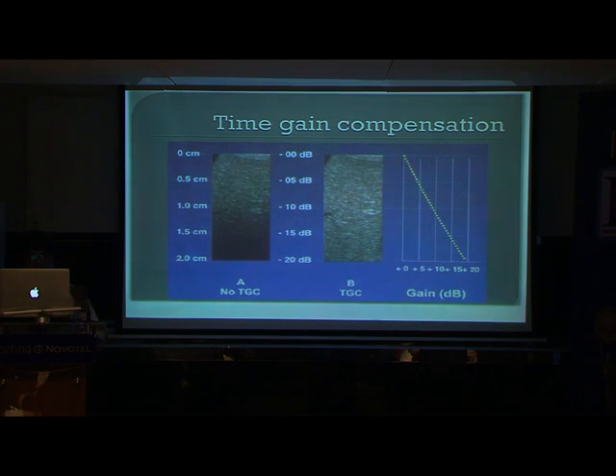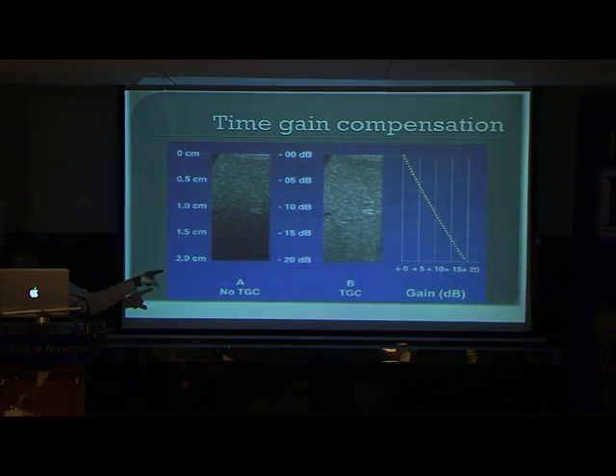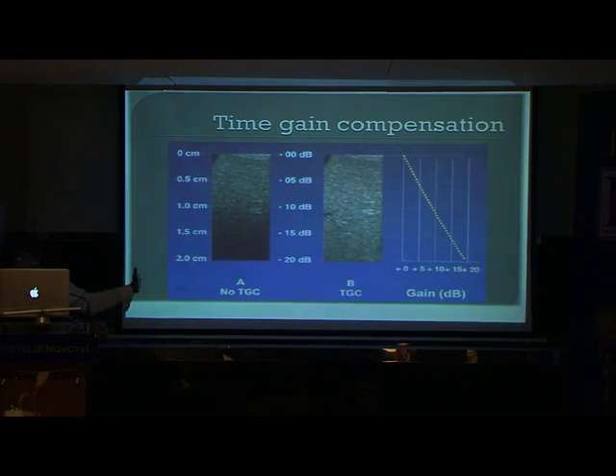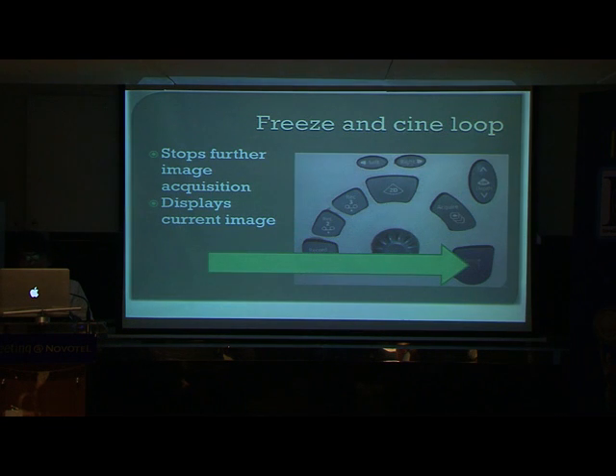Looking at a liver image: if echoes are poorly reflected from the lower part, increase the gain so the image from the lower part is equivalent to that seen in the upper part, giving a uniform image. That is the importance of time gain compensation. Finally, the freeze and cine loop function can be used for recording purposes.